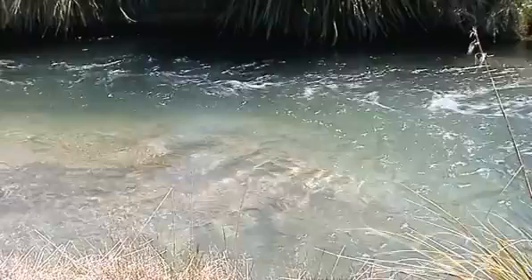From the central chamber you can hear the pump rattling away there. We pump it over to the three tanks that you can see over there, and the reason we do that is because Matt's milking twice a day. The total volume we get out of there daily is about 40,000 litres a day — 40 cubes — in two bites in the morning and afternoon milking. So we need some equalisation or buffer storage, which is why we use these tanks here. We have 90,000 litres of storage and it also provides a little bit of additional settling. We've got an automated flush valve which flushes from the tank back by gravity into the weeping wall as well.